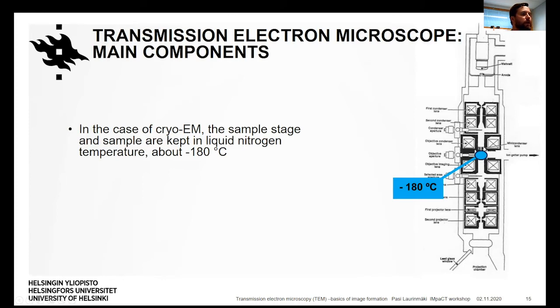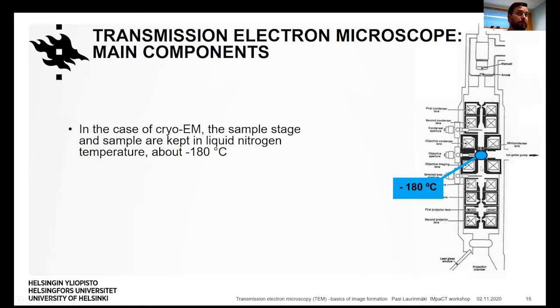In the case of cryo-EM, the sample stage and sample are kept at liquid nitrogen temperature during imaging — about minus 180 degrees Celsius. This is the main difference compared to traditional transmission electron microscopy of room-temperature specimens. When we move to cryo-electron microscopy, the key is that the sample has to be kept at liquid nitrogen temperature all the time, and the microscope has to be specially equipped with a cryo-sample holder that keeps the sample at liquid nitrogen temperature during imaging.